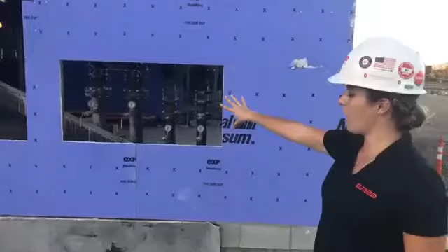Typically when you're building a chilled water system, you flush it, clean it, and then let it operate, constantly operating, so you don't really have to worry about stagnation. But we don't really know when this system is going to be operable. So we had a few sit-down meetings with the design team, with OSU, with the engineers, and worked through how we were going to keep this system isolated and safe for an indefinite period of time without degrading any of the valves or seals.